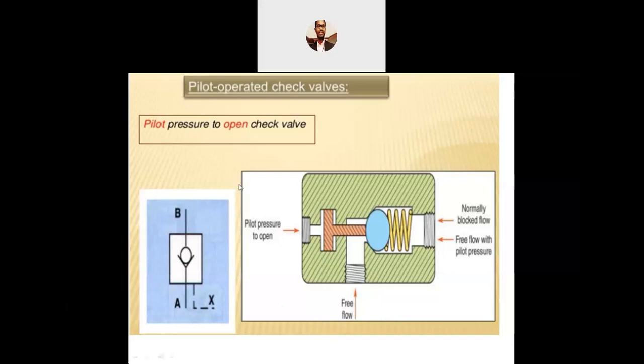Now this is the pilot-operated check valve. Pilot pressure is used to open the valve. A pilot means there is a bypass control — the pilot pressure is applied to open the valve and allow free flow. By manually operating the pilot, you can displace the poppet from its normal seating position, making the valve orifice open. In the normal blocked-flow position the valve is closed; with pilot pressure applied, you can move it to the open position for free flow.